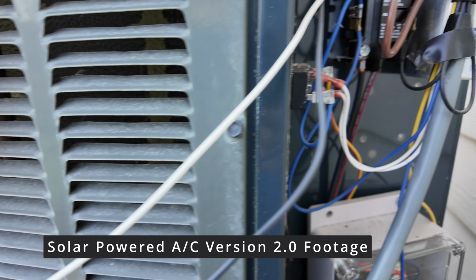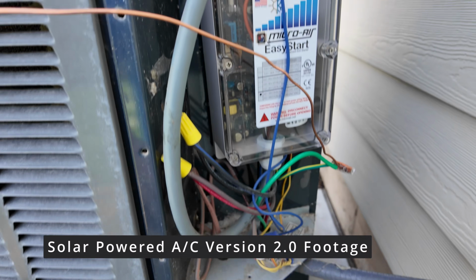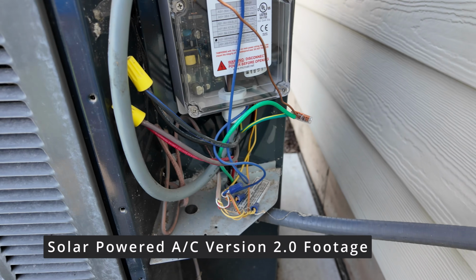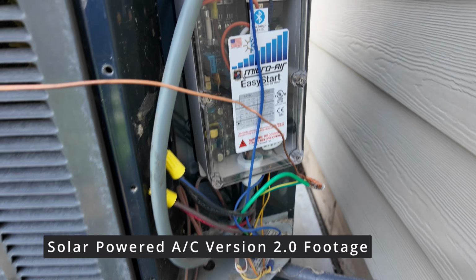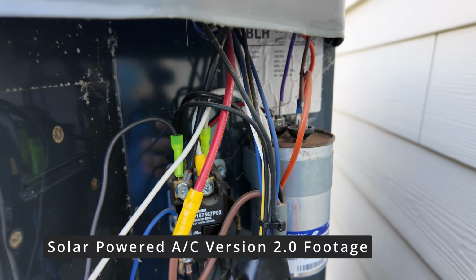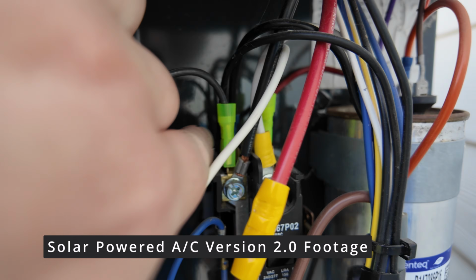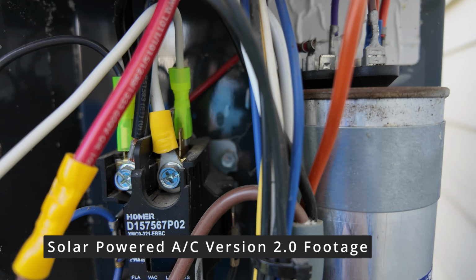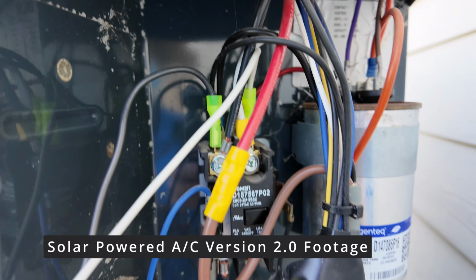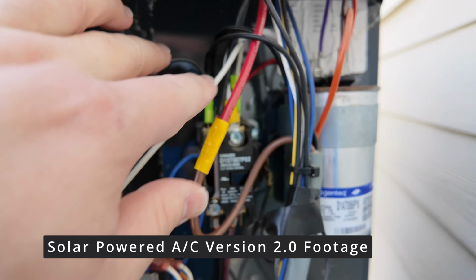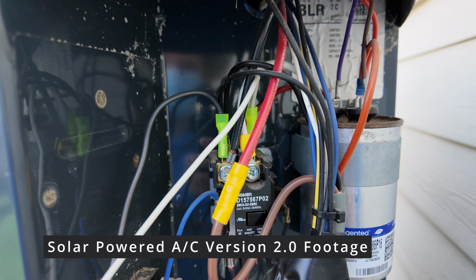Now I'm hooking this up very temporary in nature. Obviously, when you're hooking it up permanently, you need some seal tight and grommets and what have you to wire this properly. But you can see my 2 spade terminals connected to the top side of the contactor. Because this is 240 volt, it doesn't matter which side of the contactor those wires go to.